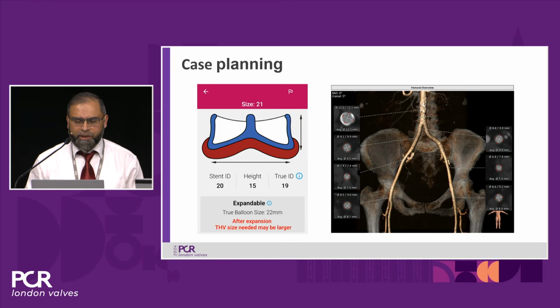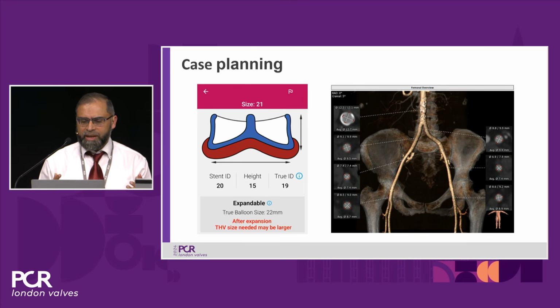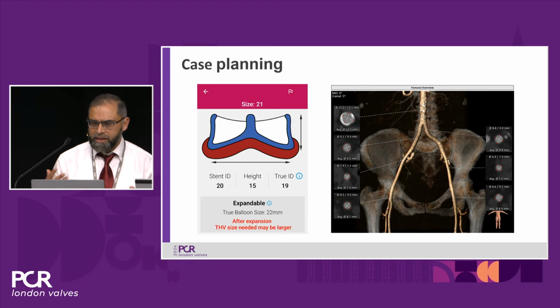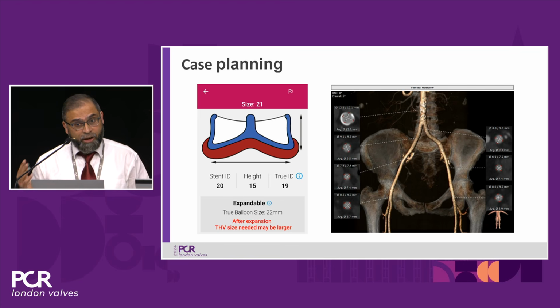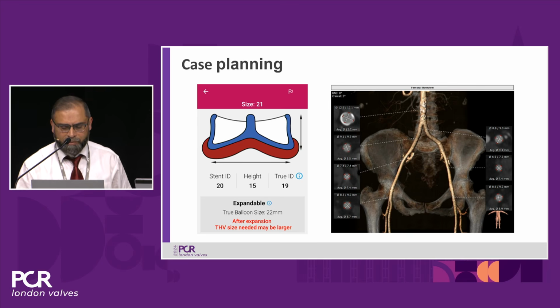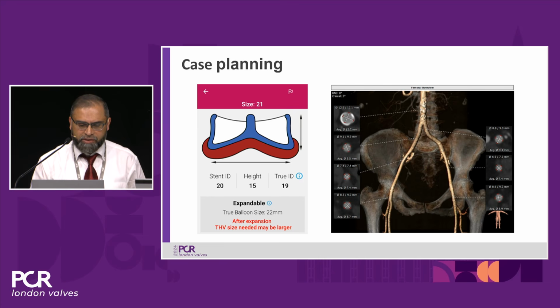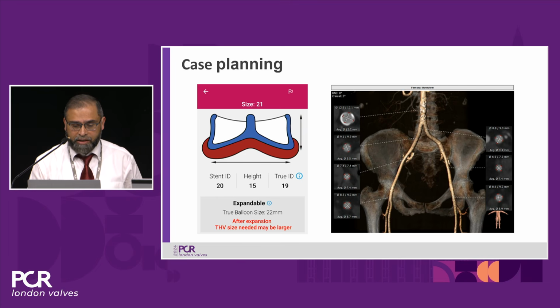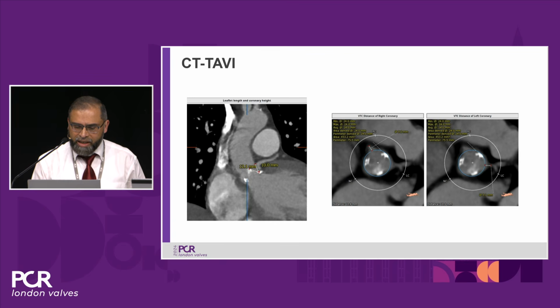It's a valve-in-valve one. We have this nice valve-in-valve app that can give you some ideas what we are dealing with. So it's a 21 millimeter valve. You can see the valve height, the true ID, what balloon you will need, what size valve you will need. On that ground, Hydra SMT is working to have the Hydra sizes on this valve-in-valve app to help with that. But yes, you can calculate based on the sizes. So this case was suitable for a 22 millimeter Hydra valve, and obviously we were going to do pre-dil and post-dil.